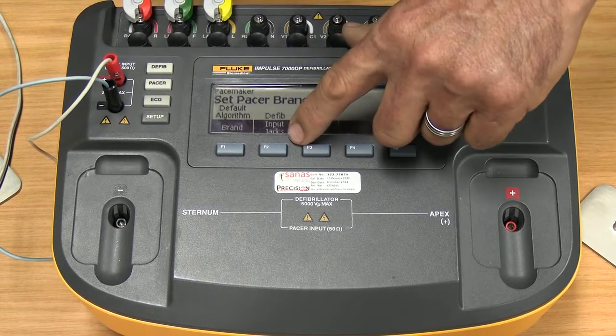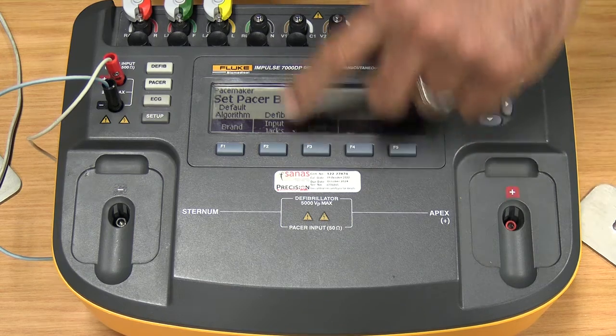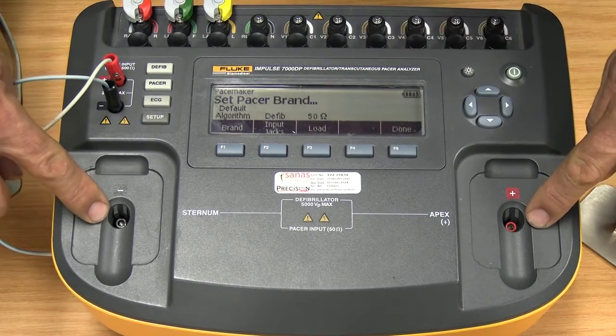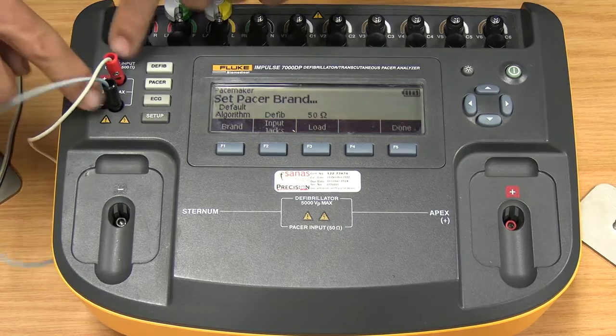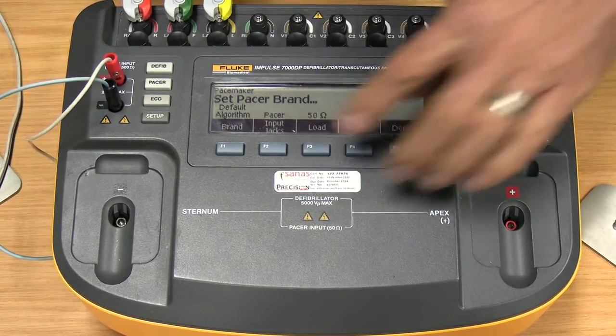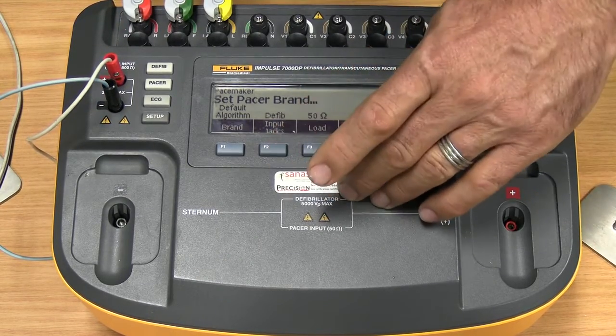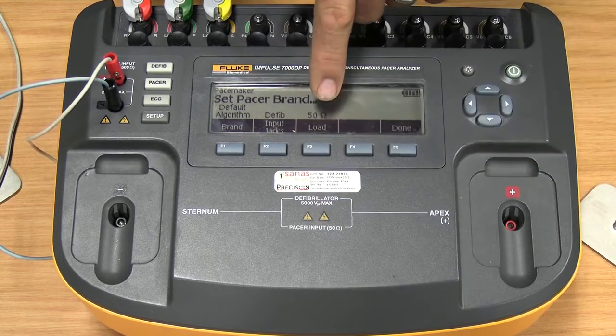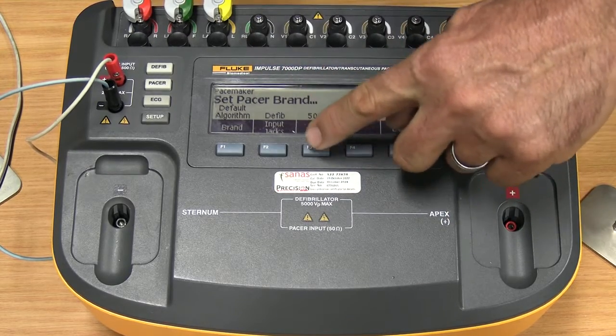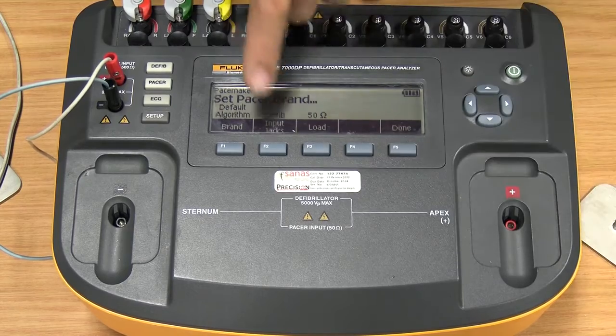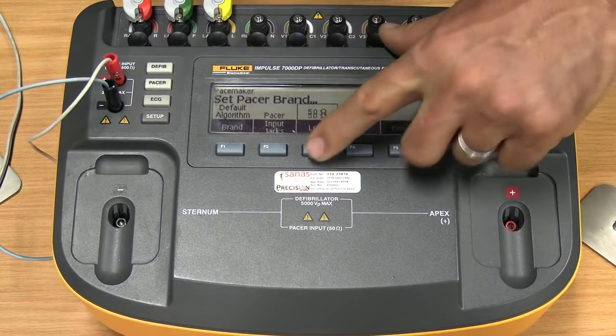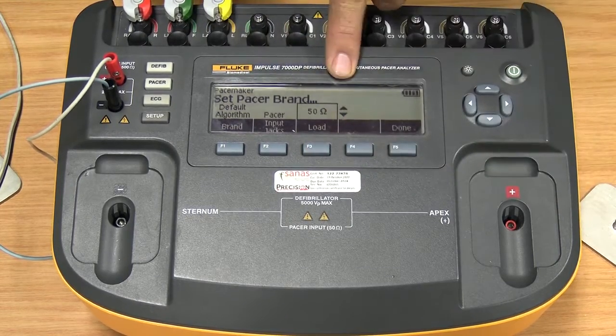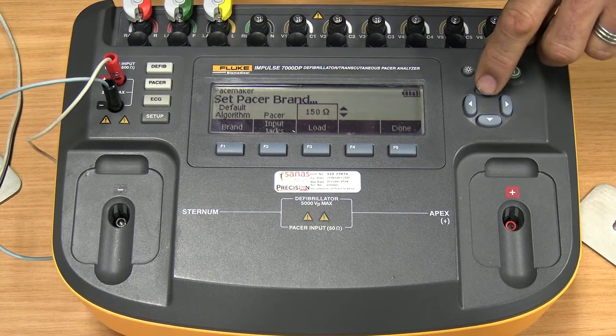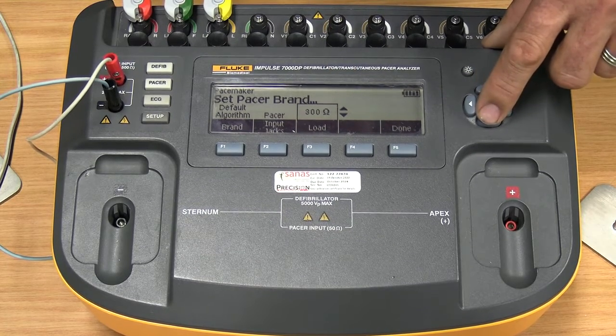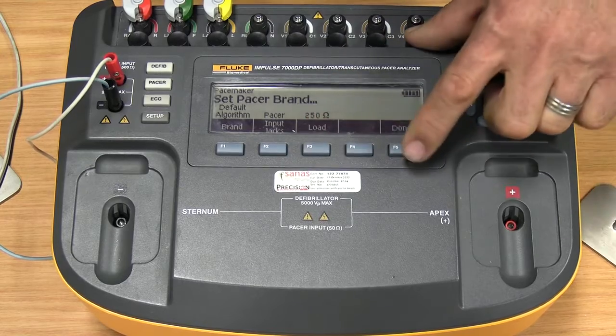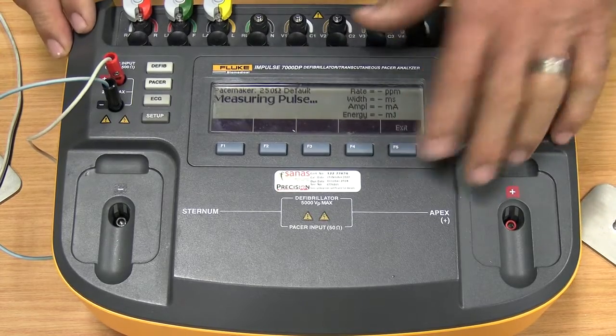Second function is our defib input jacks. Now that is what I talked about earlier on, being your defib input jack or your pacer inputs. So by pressing that function, you change between pacer and defib, pacer, defib. You'll see once we're on defib, if I go to load, which is 50 ohms, it cannot be adjusted. If I change to pacer and I go to load, you see it becomes adjustable. So from here on, I can choose between various load resistances. Okay, and done. Okay, exit.